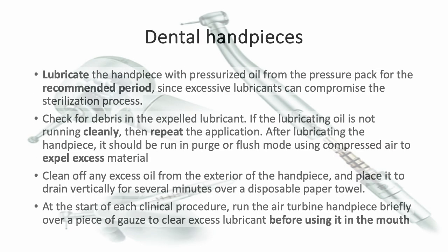After cleaning the handpiece, you should lubricate it before sterilization. Lubricate the handpiece for the recommended period. Do not excessively lubricate the handpiece because it may compromise the sterilization process. Check for debris in the expelled lubricant. If the lubricating oil is not running cleanly, then repeat the application.